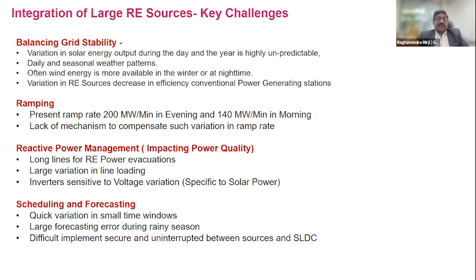We talked about ramping. Yes, I can bring some statistics there. The present ramp rate is 200 megawatt per minute in the evenings, and about 140 megawatt per minute in the morning. Ramping from 140 to 200 with such variation is not simple, and we lack a mechanism to compensate such variation quickly. That is also causing a lot of issues in the grid.